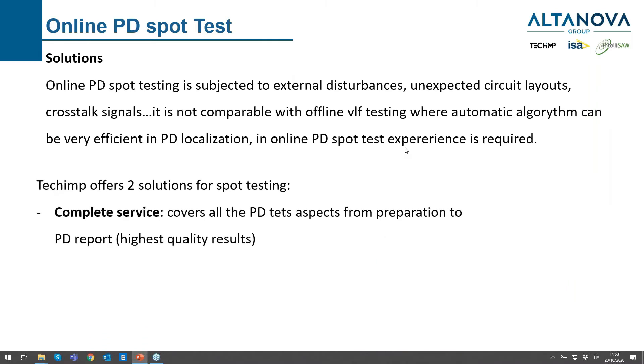In PD spot testing we have external disturbances and unexpected circuit layouts, so it's not comparable with offline testing — for example, VLF testing, which is very popular right now and is fully automated. With VLF, you only have to connect the instrument and the voltage generator together with the detection units. For efficient localization in online testing, you need some experience.